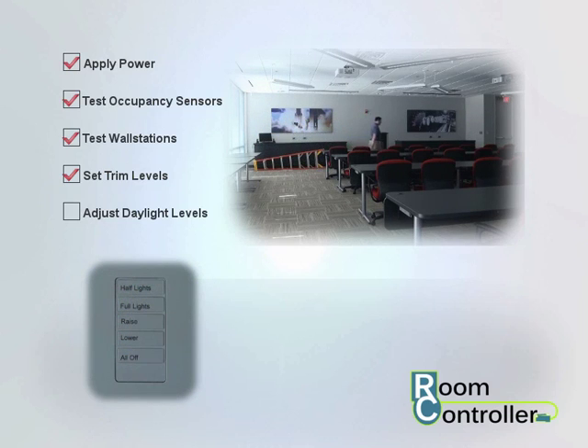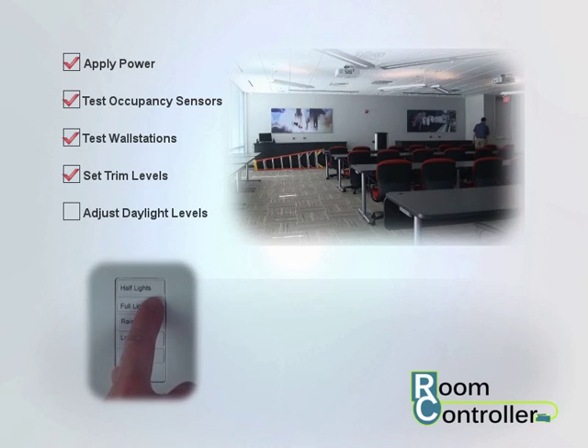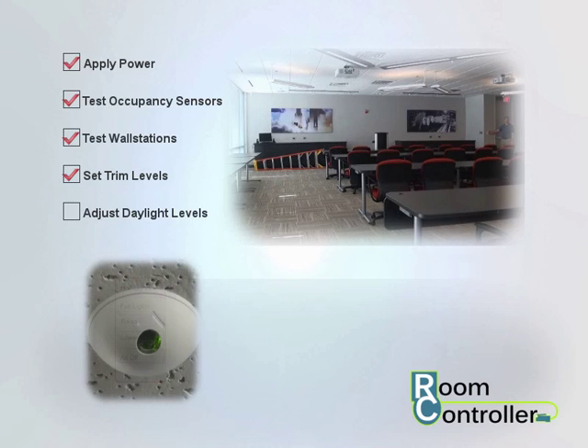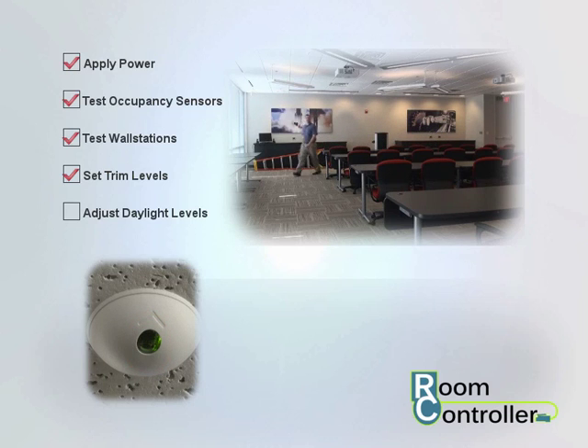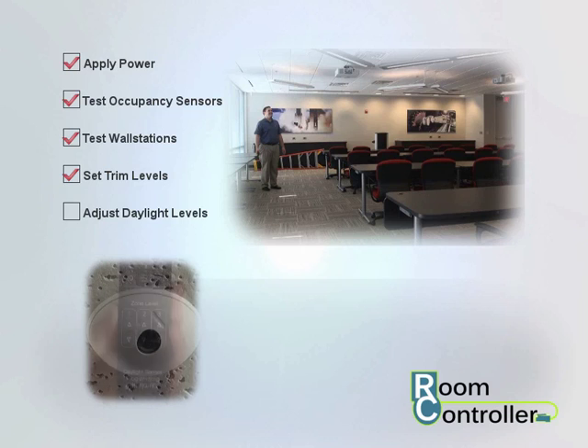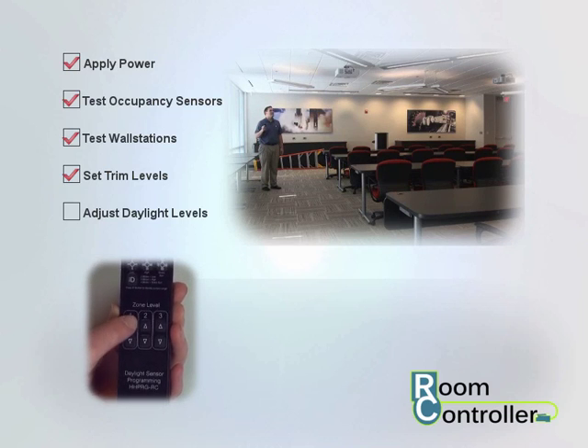Press any wall station's All Off button and then turn lighting loads on again. After lighting has been turned on, look at the daylight sensor lens. If the lens has a green LED that's on steady, refer to your installation instructions for details on making advanced daylight level adjustments. If the LED is off, point the remote at the sensor lens and press the zone's raise or lower button until the lighting is adjusted to the desired level.